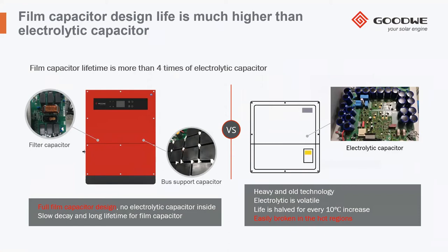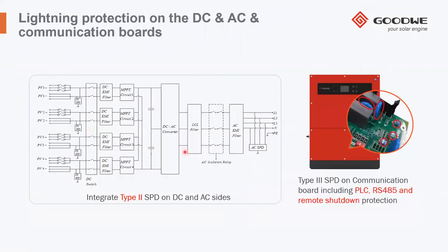Another extremely important feature is the protection against lightning on the DC and the AC side, and also on the communication boards. We have integrated type 2 SPD on the DC and the AC side, but also type 3 SPD on the communication board. So this ensures that in case of any extra lightning, you have full protection of your system. In case one of these SPDs burns, the system will anyway continue to work, even though, of course, it has to be replaced. But it's clear that this kind of protection ensures that the system is fully protected against atmospheric accidents.